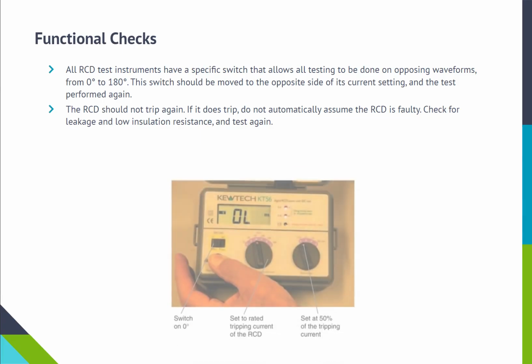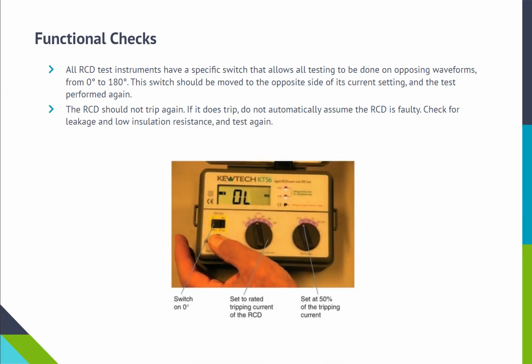All RCD test instruments have a specific switch that allows all testing to be done on opposing waveforms, from 0 degrees to 180 degrees. This switch should be moved to the opposite side of its current setting, and the test performed again. The RCD should not trip again. If it does trip, do not automatically assume the RCD is faulty. Check for leakage and low insulation resistance, and test again.